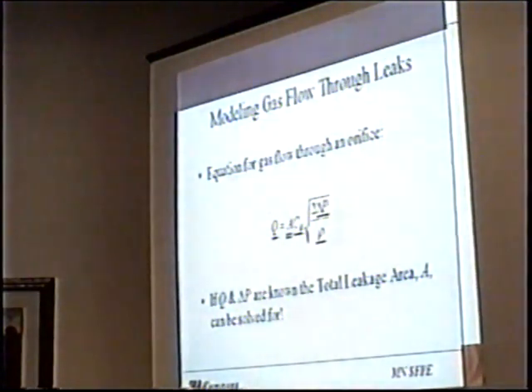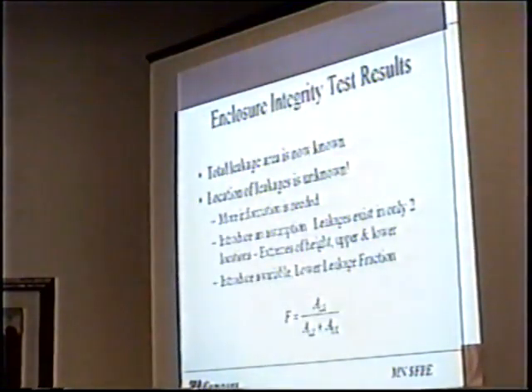So now we know we've got this existing enclosure and we've got a leakage area for it, but that area doesn't have any location. It's essentially just floating out there. It could be anywhere around the enclosure. And we know that this clean agent is typically heavier than air, except for in 1 or 2 select cases. For the most part, it's going to leak through the bottom of the enclosure. So what happens if this leakage is all on top of the enclosure? Nothing. We'll look at that in a moment, but essentially we need to know where it is.